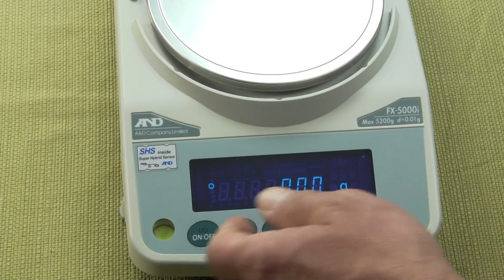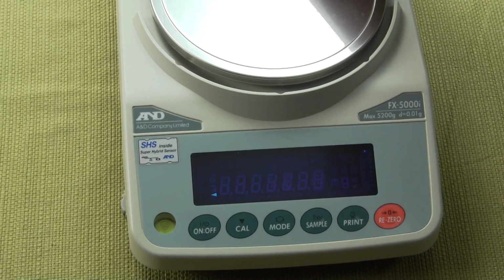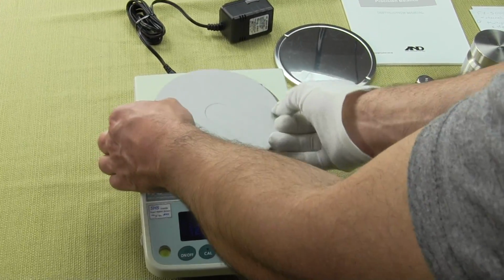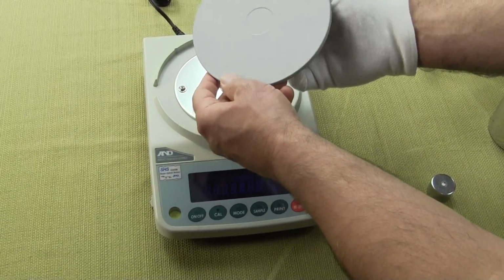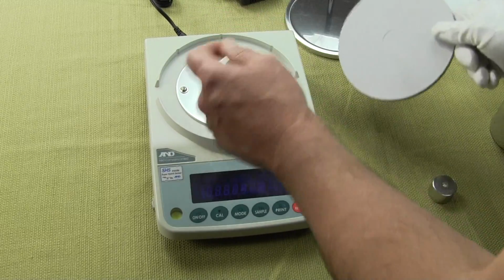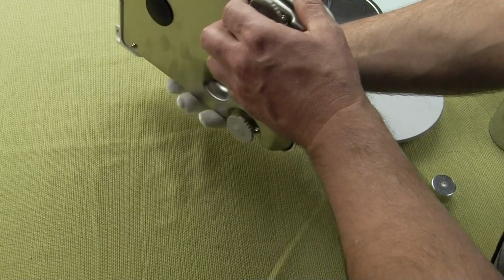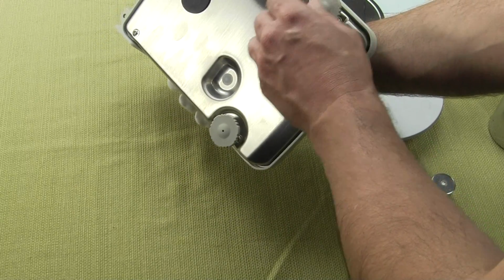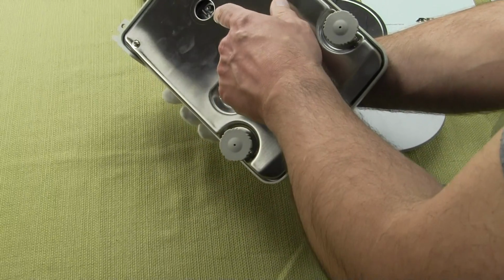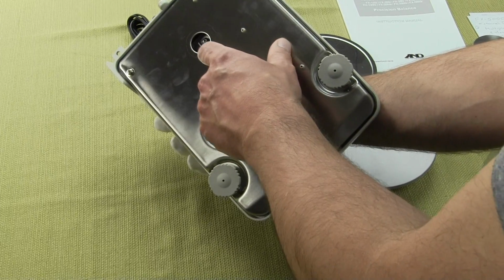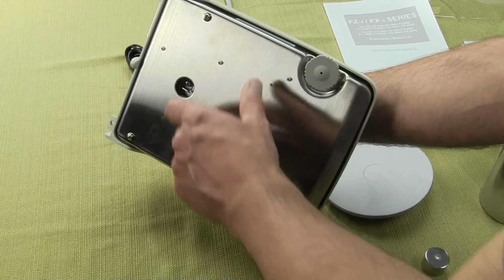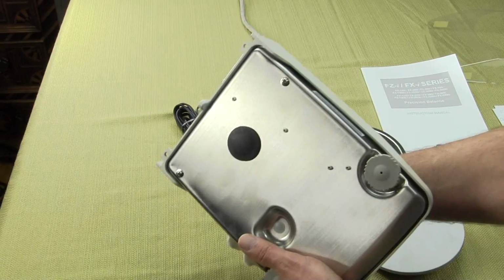Just go over a few more quick features with the balance. I'm going to shut off the balance, and I just want to show you what's behind this balance. So again, we have the weigh pan that's removable. This is only on the 5000 series. You get this nice cast aluminum pan support. On the bottom of the balance here, we have 2 adjustable feet, and we also have a port here. And on this port, this is for below-the-balance weighing. So there's a little hook. I'm not too sure if the camera can get this, but right in here there's a hook, and you would hang a wire to do the specific gravity beneath the balance or weigh in magnetic materials or hot materials. So that's a nice feature. A lot of balances in this series, that feature would not be on the balance.